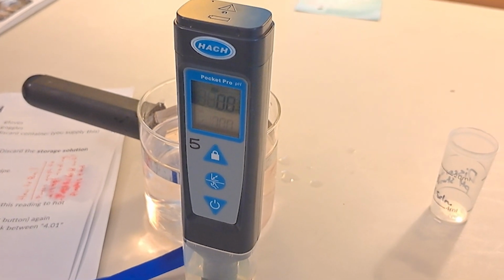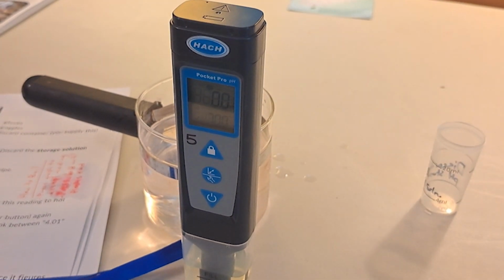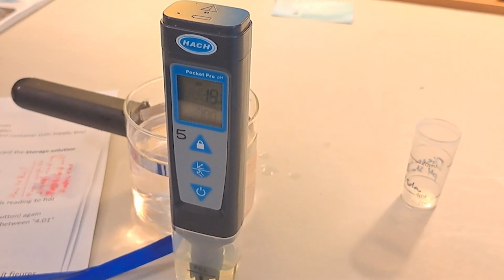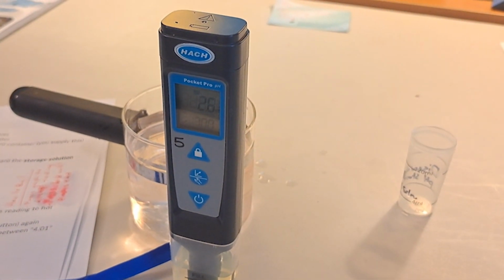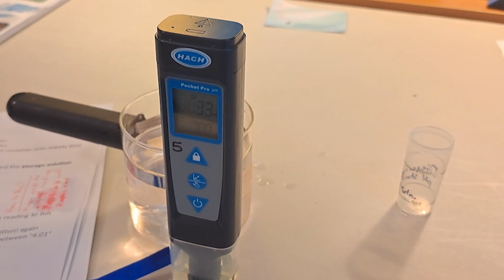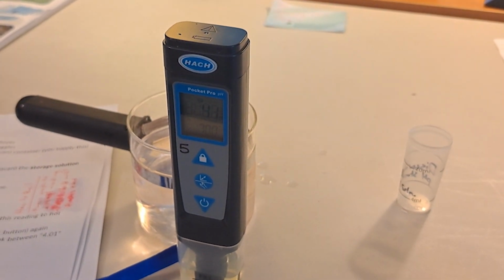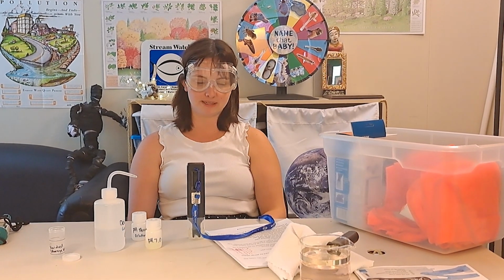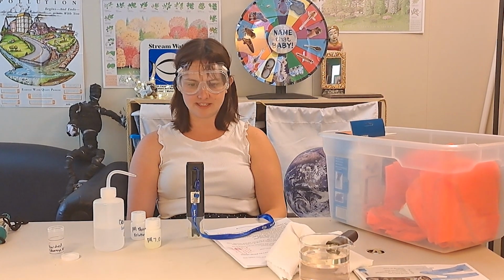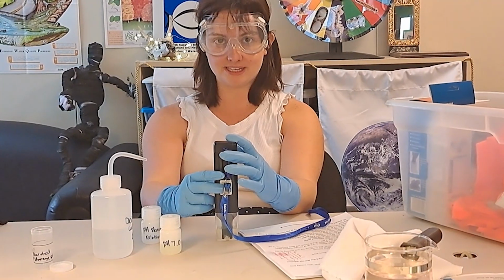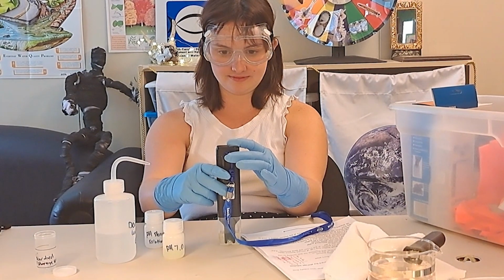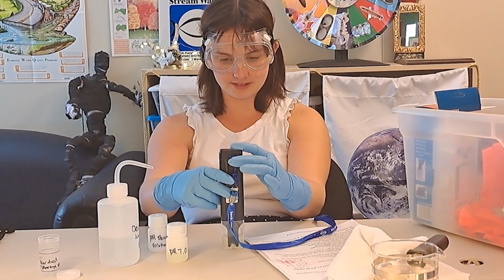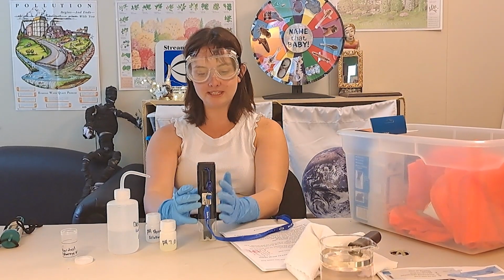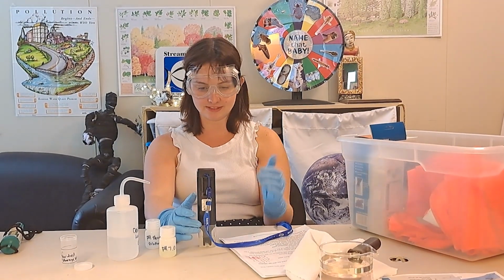It's okay if it is a little bit far from 7, like 5.2 or 8.6 or something like that. Once it stabilizes on whatever number, you press the center button and then that tells it that this is 7. So now we wait. And this can take a couple of minutes, but with 7 it doesn't take too long. So I'm stabilized at 6.8. But I want to tell the meter that this is 7. So hold down the center button to tell it this is 7.